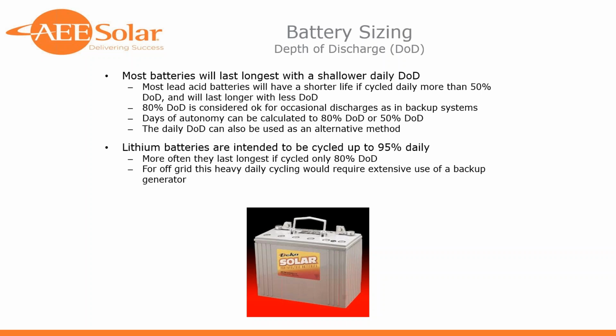For self-consumption, you're cycling it daily. You probably don't want to go more than 50% depth of discharge daily. Going to 30% depth of discharge would certainly increase the lifetime of the battery, but on the other hand, it's going to cost more. So you have to find a balance there. Lithium batteries are a little different. They are generally made to last 10 years, with a daily discharge of 80 to 90% or more. Again, they may last longer if you discharge them less than that, 80% or something. Of course, for off-grid, you're in that problem where you're having to run your backup energy source more often if you have that small amount of backup.